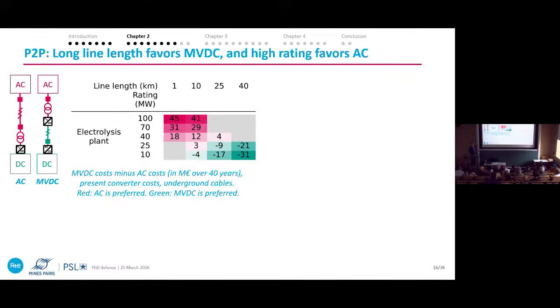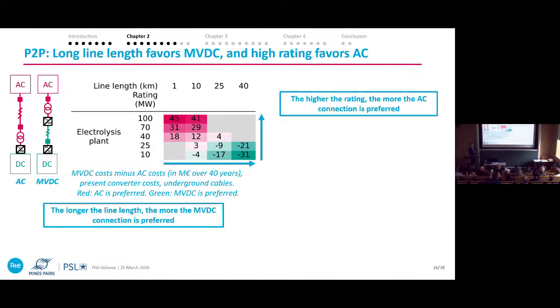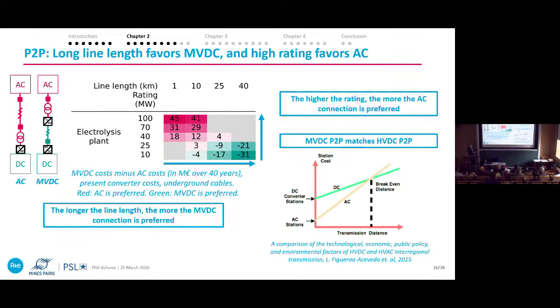Roughly, if you just want a sense of what's happening: in red, you should do AC; in green, you should do MVDC. What can be inferred is that the longer the line length, the more MVDC is preferred, the more green you see. And the higher the rating, the more AC is preferred. This is very similar to HVDC point-to-point analysis.